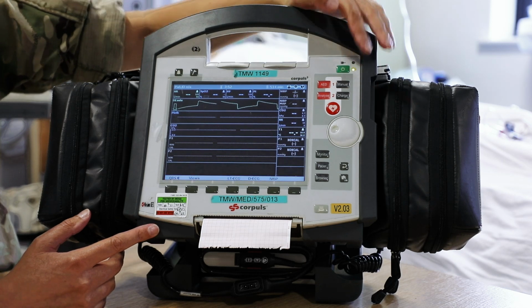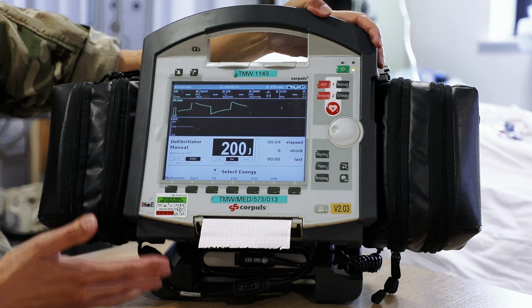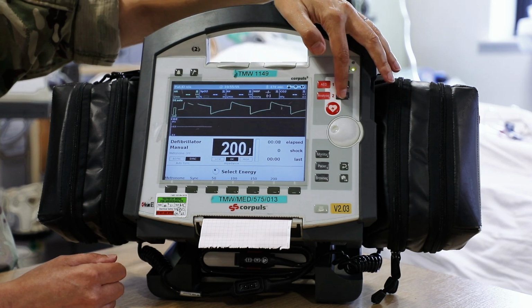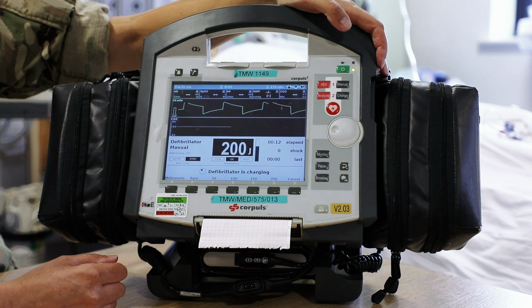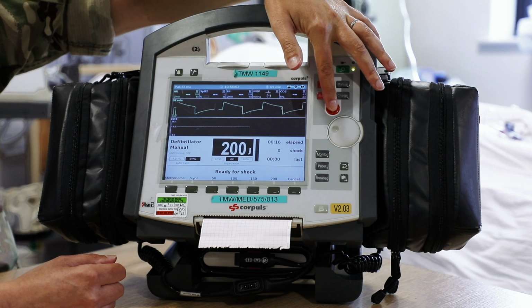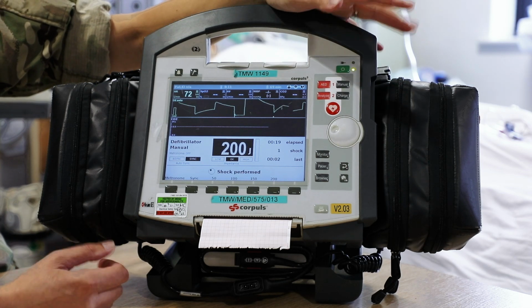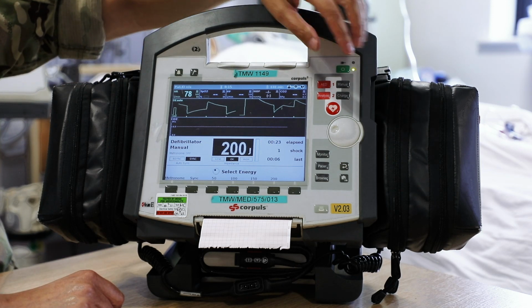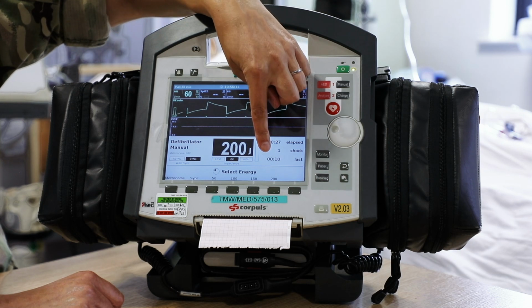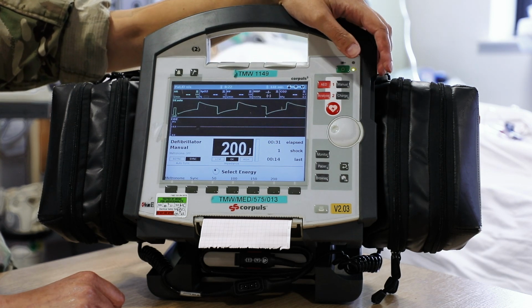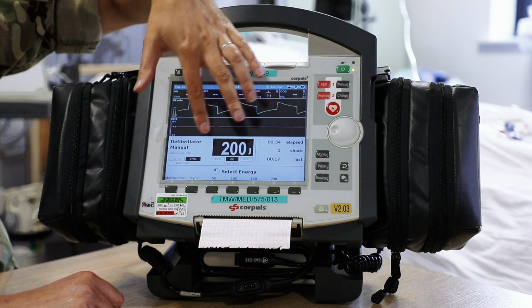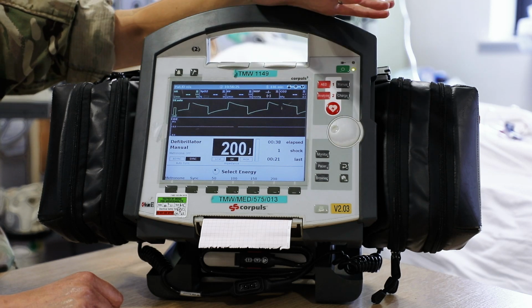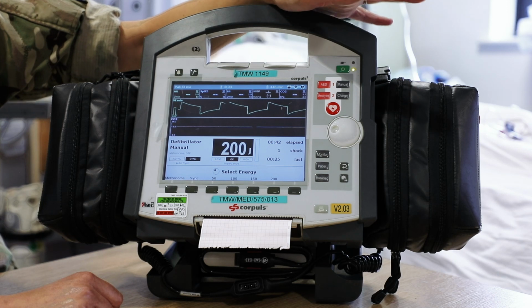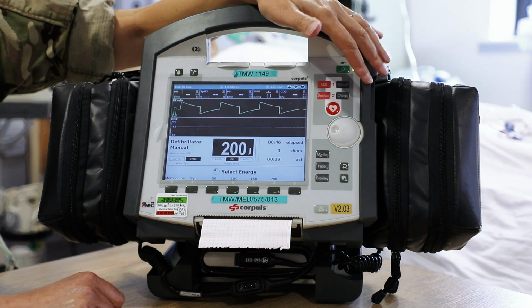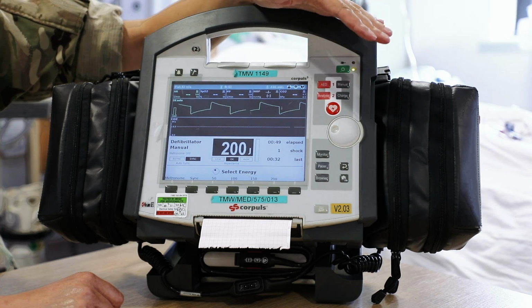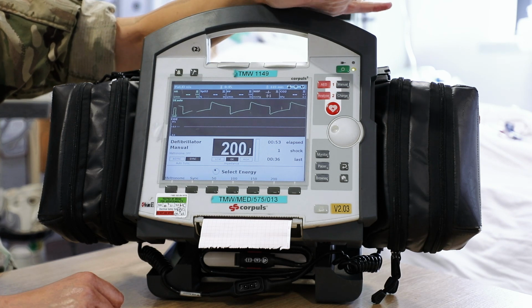So test number 2, press your manual defib button. This time we're going to simulate shocking through the patches. So this time we're going to charge up the defib at 200 joules. And we are going to press and hold the shock button to tell the machine to deliver a shock into that safety box at the bottom. You'll see that it's registered one shock has been delivered, and that countdown for the next shock has started. We're going to press and hold that for a short time, just because that's related to our auto sync function, because it's going to double check that there isn't any electrical activity that would indicate that the patient needs cardioverting rather than defibrillation. So just press and hold, and in a matter of seconds it will shock the patient. So that's test number 2 complete.